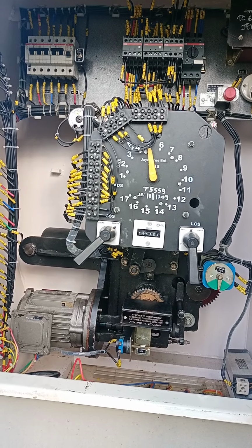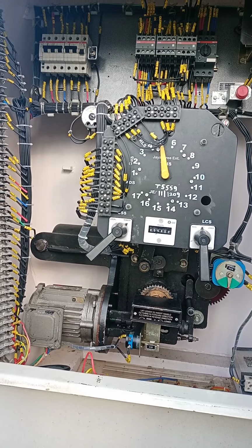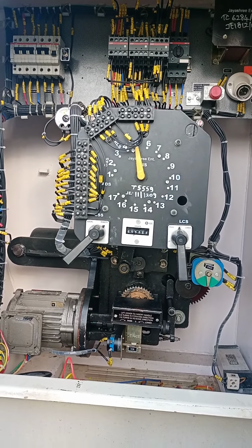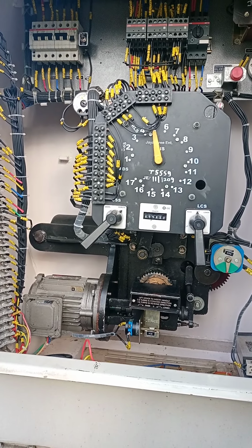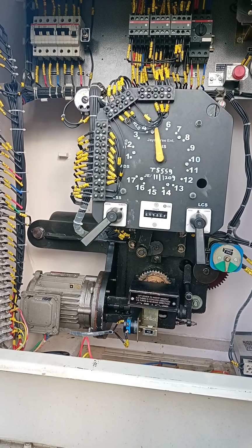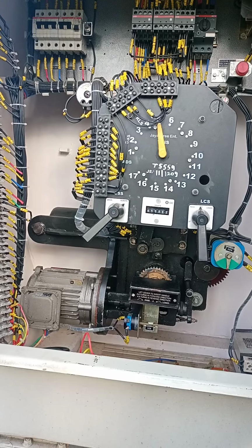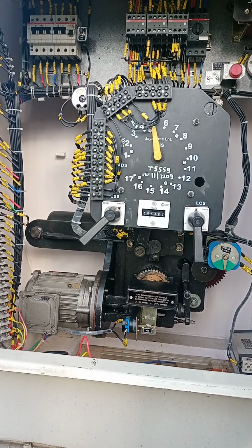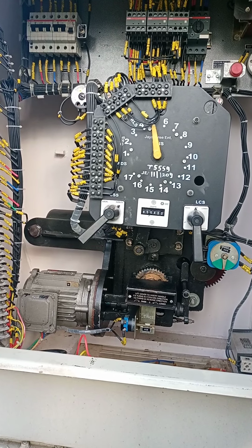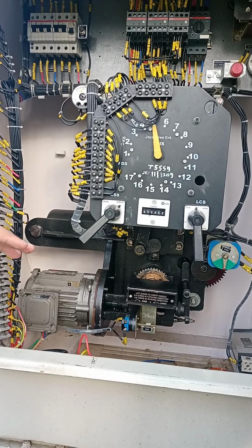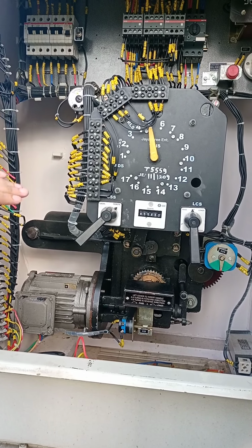And the third interlock is the tripping interlock. This is for the case where your tap position gets stuck. For example, you are increasing the tap from 3 to 4. There is a time limit for going from 3 to 4. At our place we have a time of 5 seconds. If it goes beyond that time, it means your tap has been stuck. In that case it will trip and thus protect the transformer.